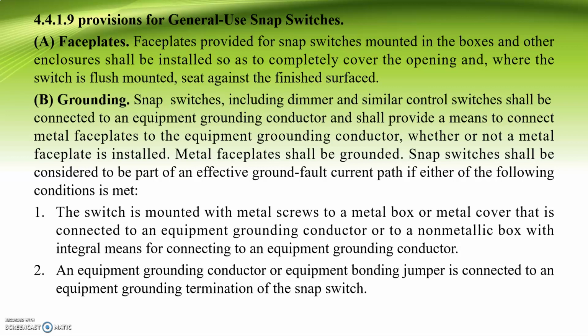Snap switches shall be considered to be part of an effective ground fault current path if either of the following conditions is met. The switch is mounted with metal screws to a metal box or metal cover that is connected to an equipment grounding conductor, or to a non-metallic box with integral means for connecting to an equipment grounding conductor. Or, an equipment grounding conductor or equipment bonding jumper is connected to an equipment grounding termination of the snap switch.